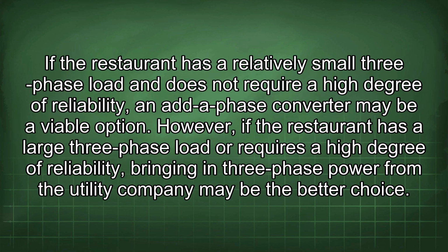Based on the specific requirements of the restaurant, one option may be more cost-effective than the other. If the restaurant has a relatively small three-phase load and does not require a high degree of reliability, an add-a-phase converter may be a viable option. However, if the restaurant has a large three-phase load or requires a high degree of reliability, bringing in three-phase power from the utility company may be the better choice.